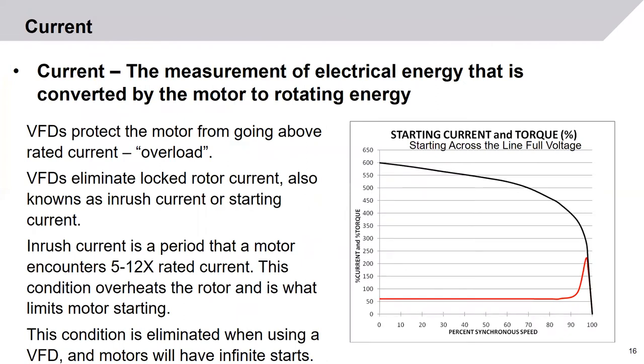Current is the measurement of electrical energy that is converted by the motor to rotating energy — the motor converts electrical current to output horsepower. VFDs protect the motor from going above its rated current or going into excess overload. VFDs eliminate locked rotor current, also known as inrush current or starting current. Inrush current is a period where a motor encounters 5 to 12 times its rated current. This condition will overheat the rotor and is what limits motor starting.